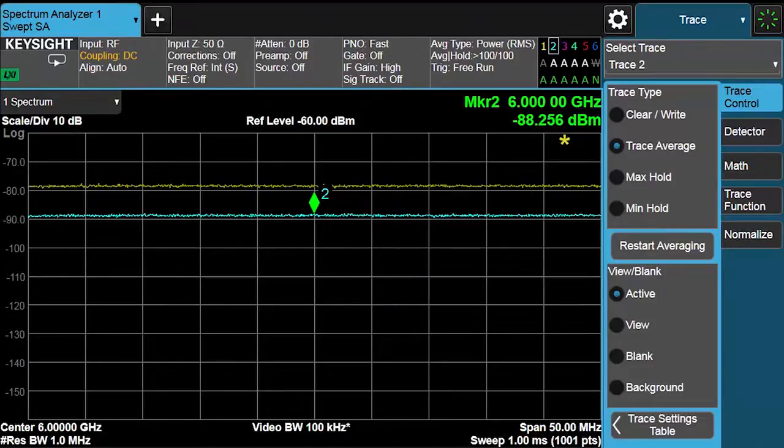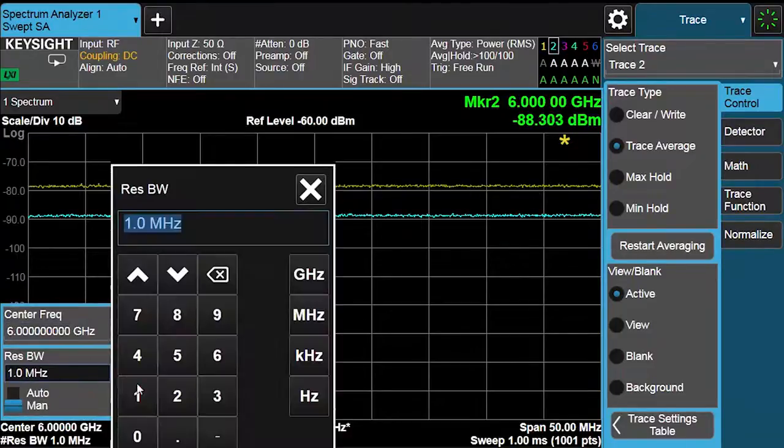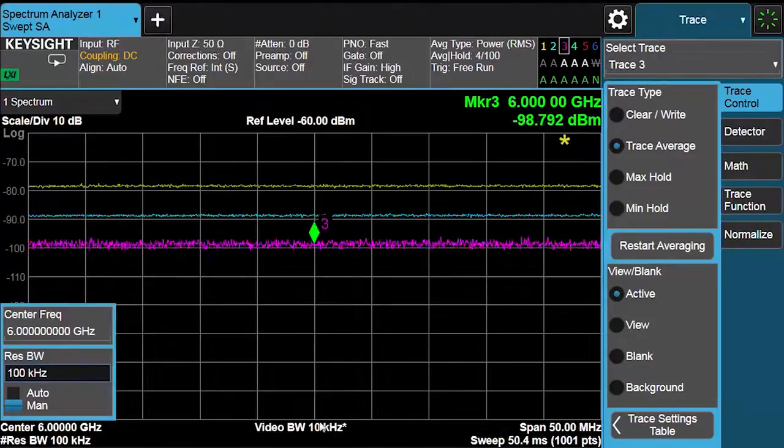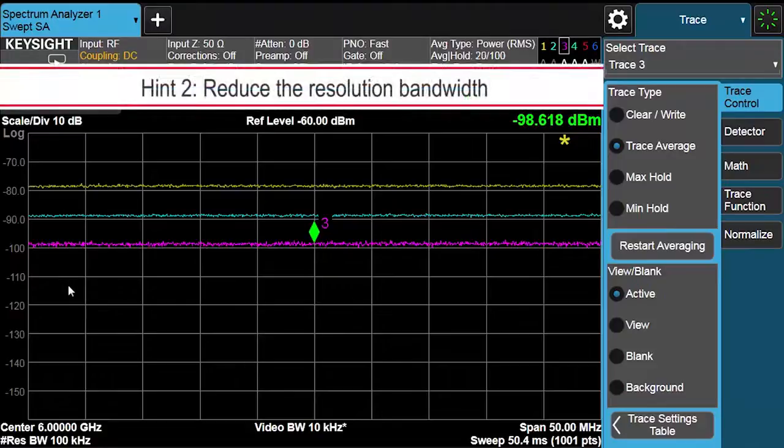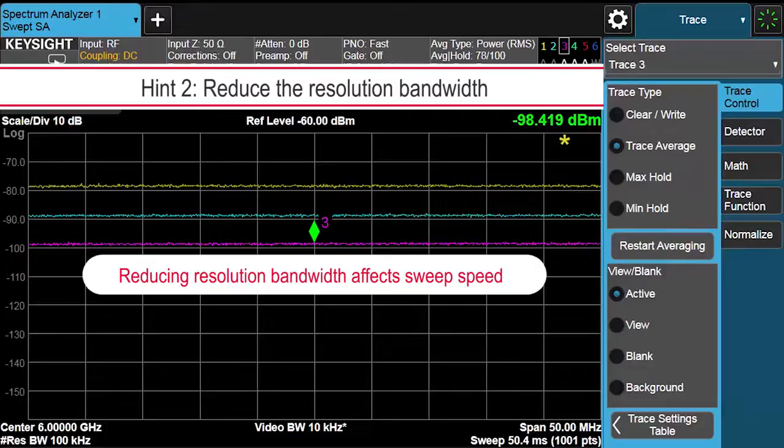So next, I'll go ahead and change the resolution bandwidth setting from 1 MHz to 100 kHz. This is a reduction by a factor of 10. And now you can notice that the noise floor has also dropped by a factor of 10. We're now sweeping at 50.4 ms versus the previous 1 ms sweep speed. So a reduction in the resolution bandwidth setting does affect your sweep speed.